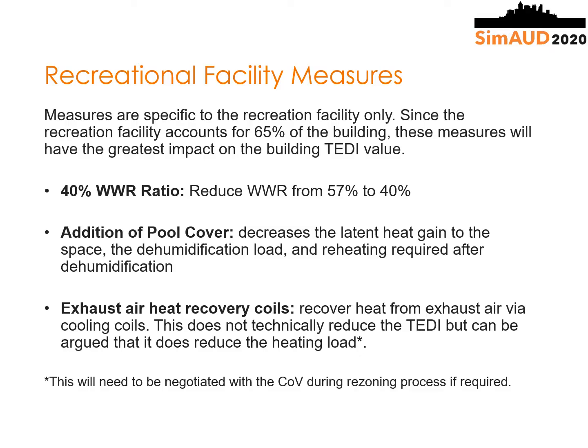First, we'll start looking at the measures that are specific for the recreational facility. The first measure we'll look at is reducing the window to wall ratio from 57% to 40%. Then we'll look at the addition of a pool cover, which decreases the latent gain to the space, the dehumidification load, and reheating required after dehumidification. We'll also look at exhaust air heat recovery coils. That's where heat is recovered from the exhaust air via cooling coils. This does not technically reduce the TEDI, but can be argued that it does reduce the heating load.